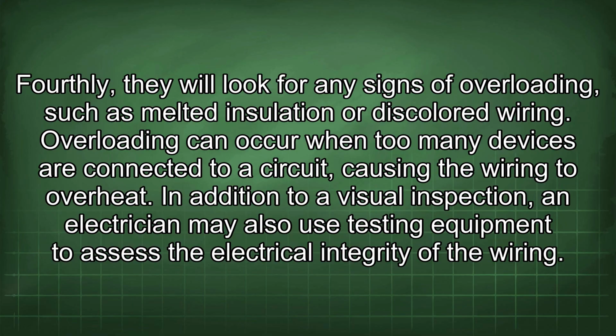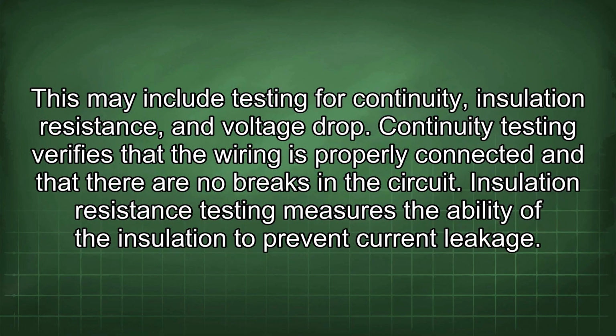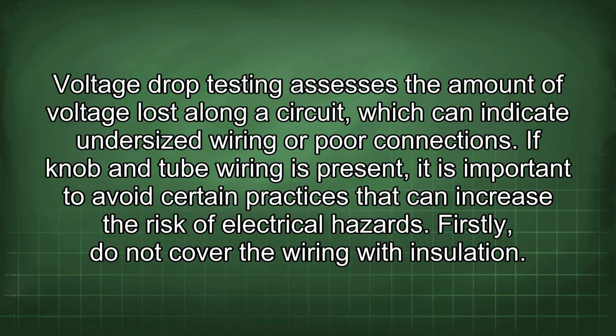In addition to a visual inspection, an electrician may also use testing equipment to assess the electrical integrity of the wiring. This may include testing for continuity, insulation resistance, and voltage drop. Continuity testing verifies that the wiring is properly connected and that there are no breaks in the circuit. Insulation resistance testing measures the ability of the insulation to prevent current leakage. Voltage drop testing assesses the amount of voltage lost along a circuit, which can indicate undersized wiring or poor connections.